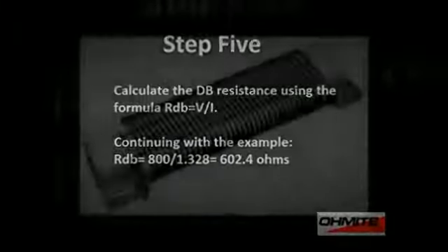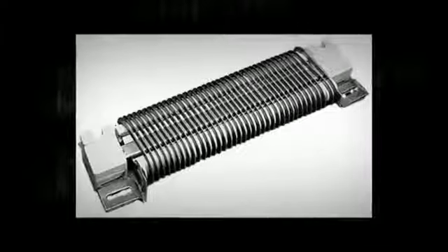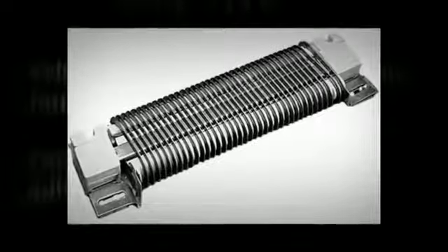Select a resistor bank that has all of the following: a resistance value that is less than the value calculated, R DB in ohms, and a resistance value that is greater than the minimum resistance and power value.